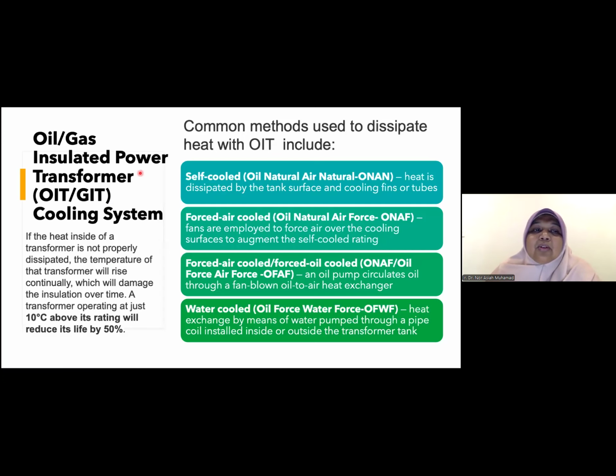Okay, so we also have gas insulated transformers. If oil, we call it oil insulated. We also have gas insulated. The purpose is the same, as a cooling medium and also as an insulating material. The difference is that we are using oil or gas. So transformers for oil can be categorized into four. It depends on what support is used to make the oil cool.